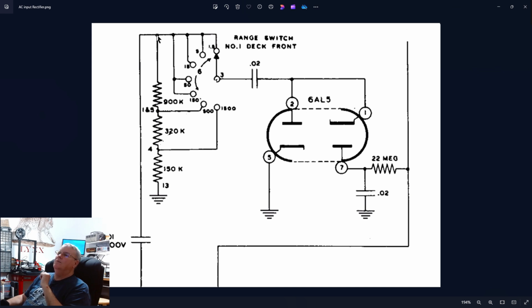The AC signal comes up and here's another array of resistors, think of them as a pre-scale. This is the same range switch down there, just another wafer on it. What happens is if you go up to 150 volts, it doesn't pre-scale. But when you start trying to use the 500 or the 1500 volt scale, you need to knock the voltage down even more. So it uses this to pre-scale the value down ahead of time.